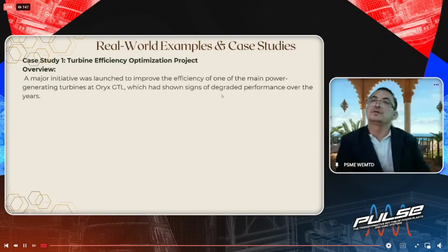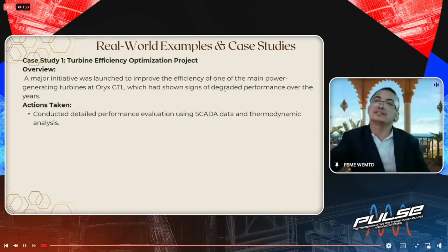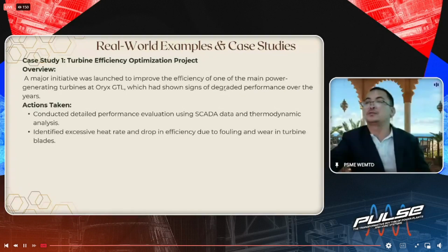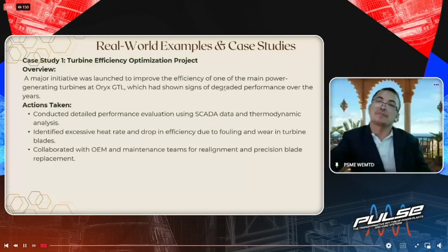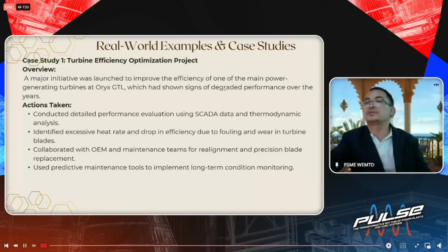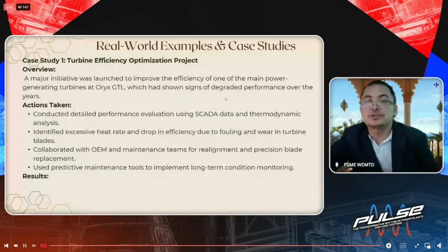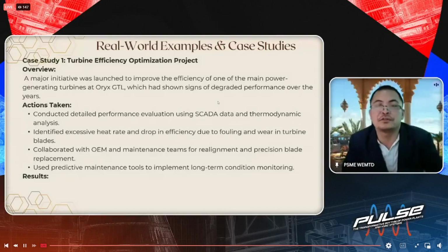A major initiative was launched to improve efficiency in one of the main power generating turbines at Oryx GTL, which had shown signs of degraded performance over the years. Action taken: conducted a detailed performance evaluation using SCADA data and thermodynamic analysis, and identified excessive heat rate and drop in efficiency due to fouling and wear in turbine blades. Then collaborated with OEM and maintenance teams for realignment and precision blade replacements, and used predictive maintenance to implement long-term condition monitoring. So the degraded turbine at Oryx GTL was upgraded using SCADA data and predictive tools.